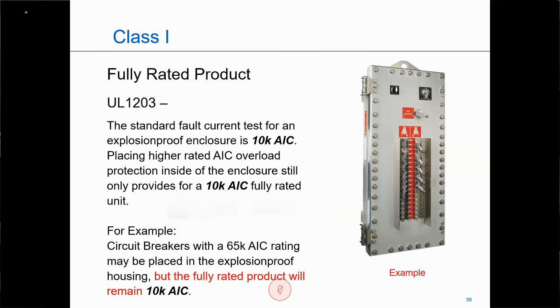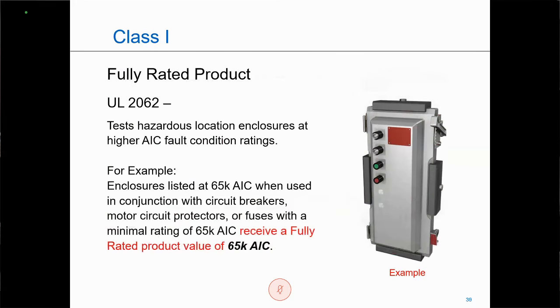But when there is an explosion caused by fault current, there are also electromagnetic effects that happen inside the enclosure. So you get that attraction and repelling with the electromagnetic effects, and that affects the flame path differently. So to have an entire unit rated for the particular AIC rating that you require for that project, the manufacturer needs to test to UL 2062. So in this particular case, the internal components can be installed, matching the required AIC rating, and the enclosure will also be approved for that particular AIC rating.